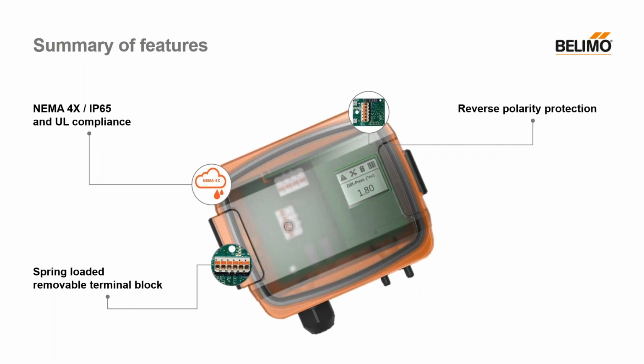As I mentioned, and I'm sure most of you know, all of our sensor enclosures are NEMA 4X and IP65 rated. They're all UL compliant. They have something called reverse polarity protection. So if you're using DC voltage and you get the polarity reversed, it won't damage the sensor. And again, instead of using wire nuts or any other kind of screw style connection, all of our sensors have spring-loaded terminal blocks that can be removed from a set of pins, wired up in your hand, and then plugged back into the sensor.